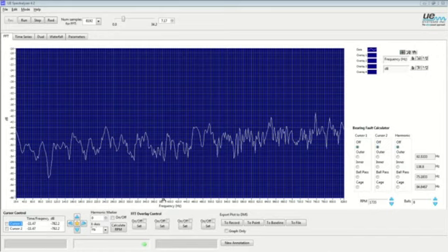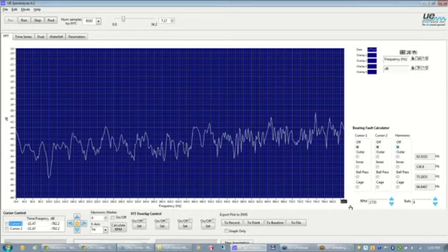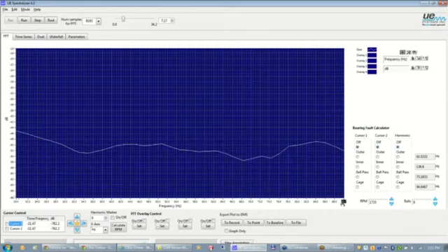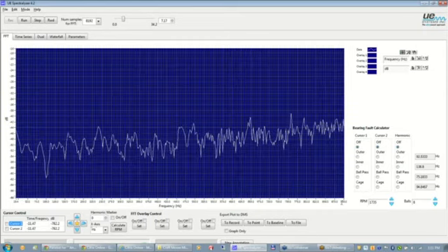On the bottom axis here, where the frequency is displayed from the heterodyne signal, I set this up by double-clicking the last number in the graph, and anywhere between 8 and 900, and I'll set this to 900 for right now, is adequate and has the most useful data that we utilize for the electrical applications. So for the purposes of that, we will set this up at 900.